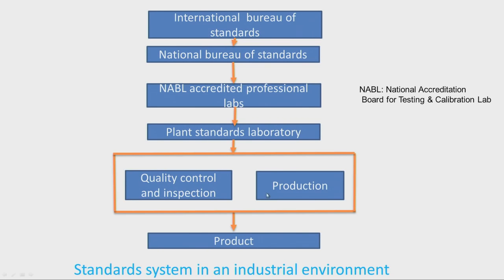In the manufacturing area, components are produced, assembled, and the final product is obtained. During production, the quality control department inspects all components. Due to continuous usage, instruments are subjected to wear and measurement error creeps in. To eliminate this, at regular intervals we compare all workshop instruments with the plant standards laboratory equipment, which are of higher accuracy. By comparing, we can determine the amount of error in the measuring instrument, which is noted on the instrument.